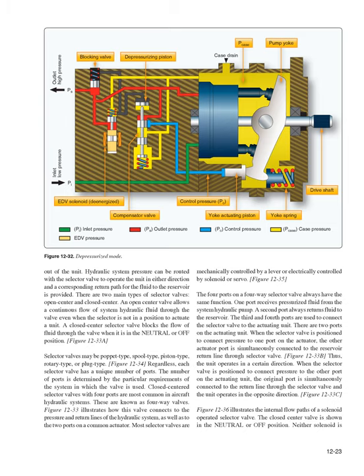There are two ports on the actuating unit. When the selector valve is positioned to connect pressure to one port on the actuator, the other actuator port is simultaneously connected to the reservoir return line through the selector valve. Figure 12-33B. Thus, the unit operates in a certain direction. When the selector valve is positioned to connect pressure to the other port on the actuating unit, the original port is simultaneously connected to the return line through the selector valve, and the unit operates in the opposite direction. Figure 12-33C.